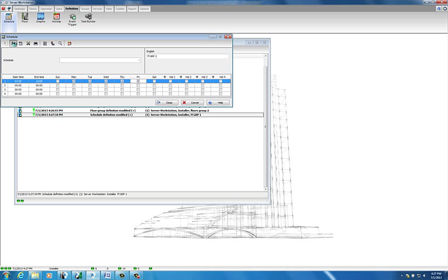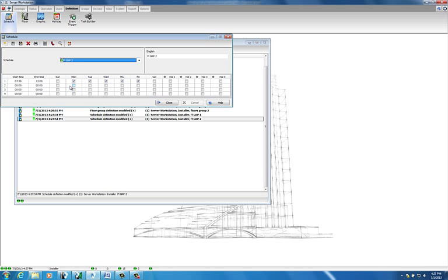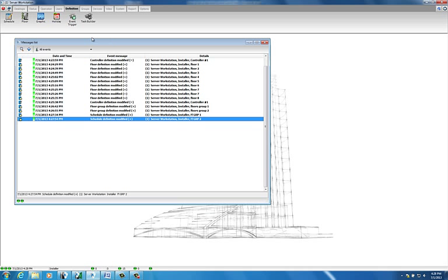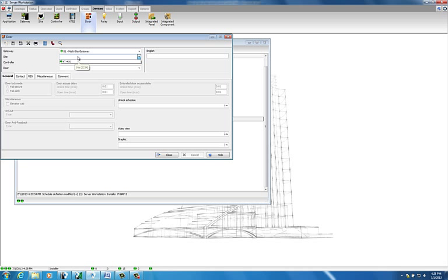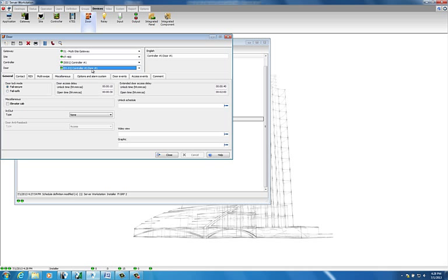So now our schedules are defined, our floor groups are defined, our floors are defined, our elevator equipment is defined. The next thing we need to do is go to the devices, doors. On the devices doors, we're going to select our gateways, then select our sites, KT-400, select our controller, and then select your door number 1. Door number 1 is going to be cab number 1. Very important, on the miscellaneous tab, check the elevator cab. Once the elevator cab is checked, we can save that.